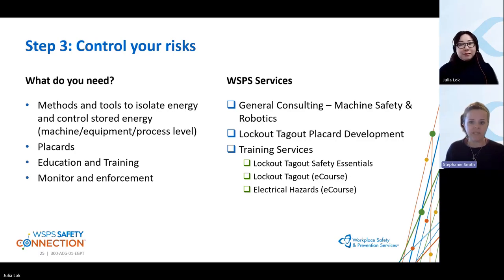When I did it at my last facility, what we did was we went through and looked at maintenance specifically, and we actually went through further and said for troubleshooting, you would lock out this source and this source. If you're doing pneumatic troubleshooting, you need pneumatic, but you can turn off this. If you need this, you can turn off this and have this.